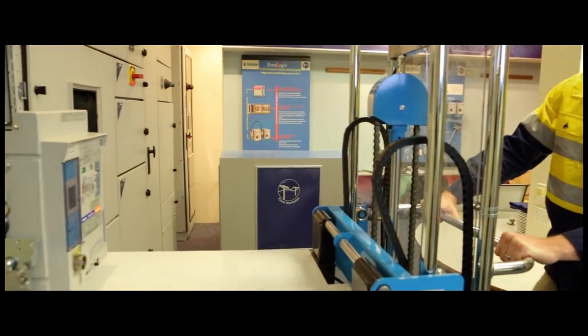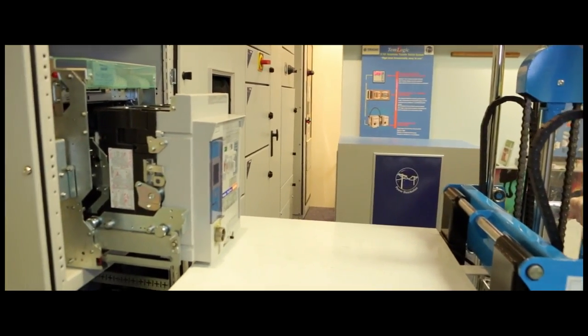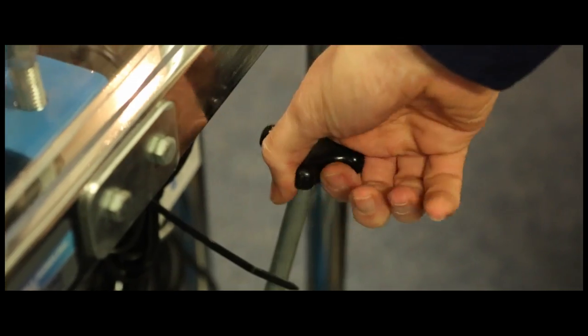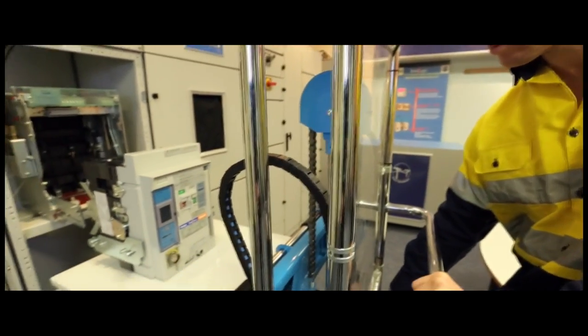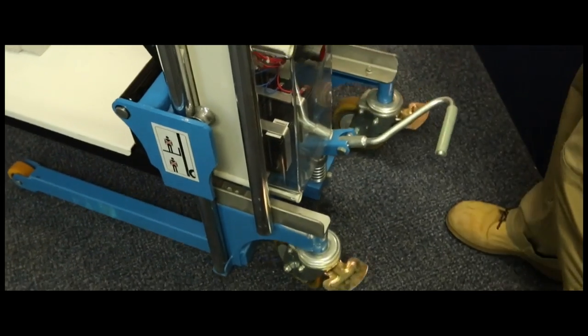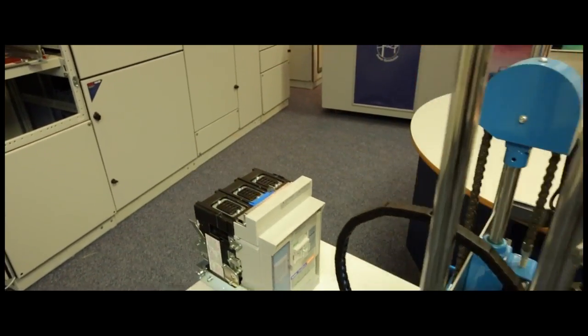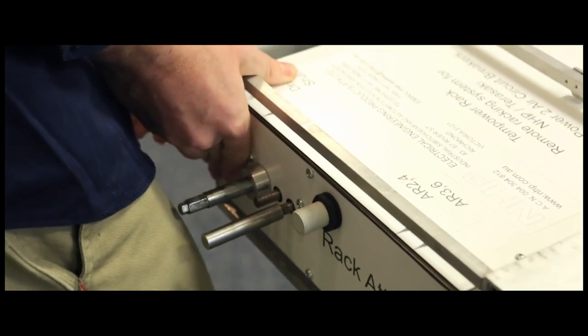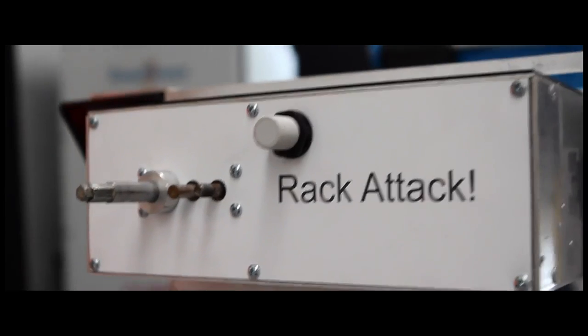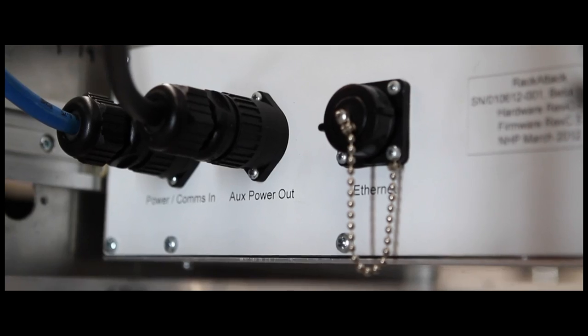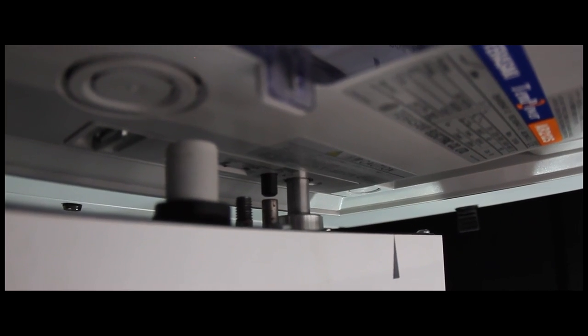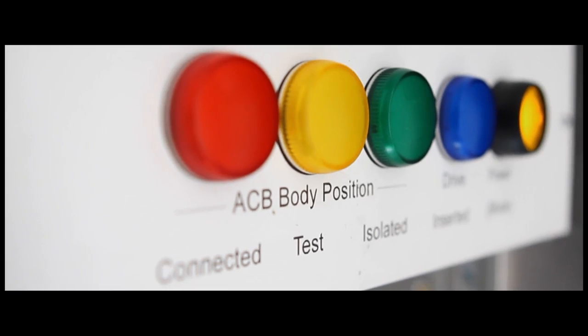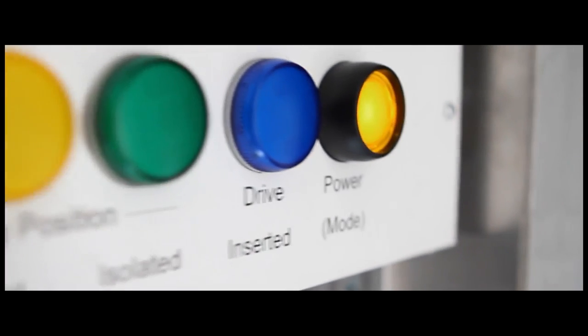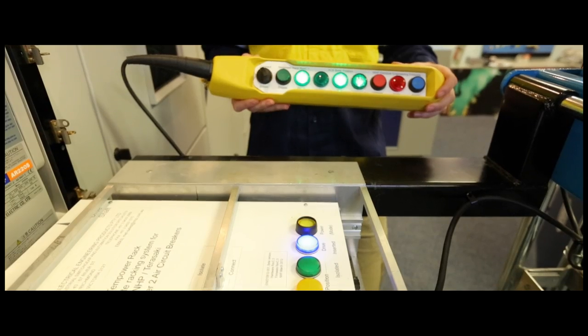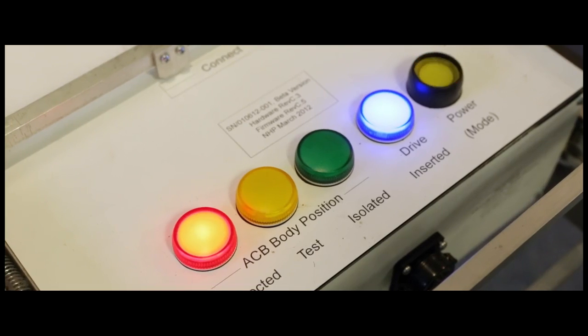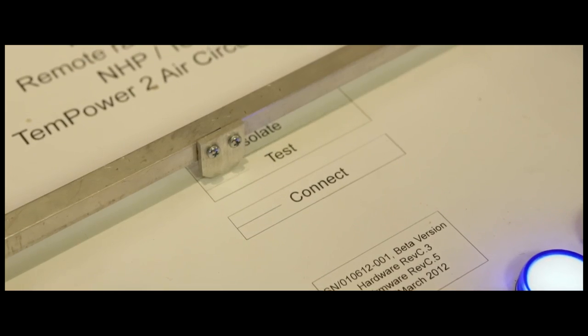The TemPower Rack features a lifting trolley for safe lifting and transport of ACB bodies. This trolley is rated to 400 kilograms and easily lifts all ACB body sizes. The TemPower Rack drive is mounted onto the secure platform of the lifting trolley. The drive mechanism is controlled via a PLC and features a number of feedback sensors to ensure correct position indication and prevent any damage to switchgear. The drive mechanism includes indication lamps to show position and other feedbacks to the user.